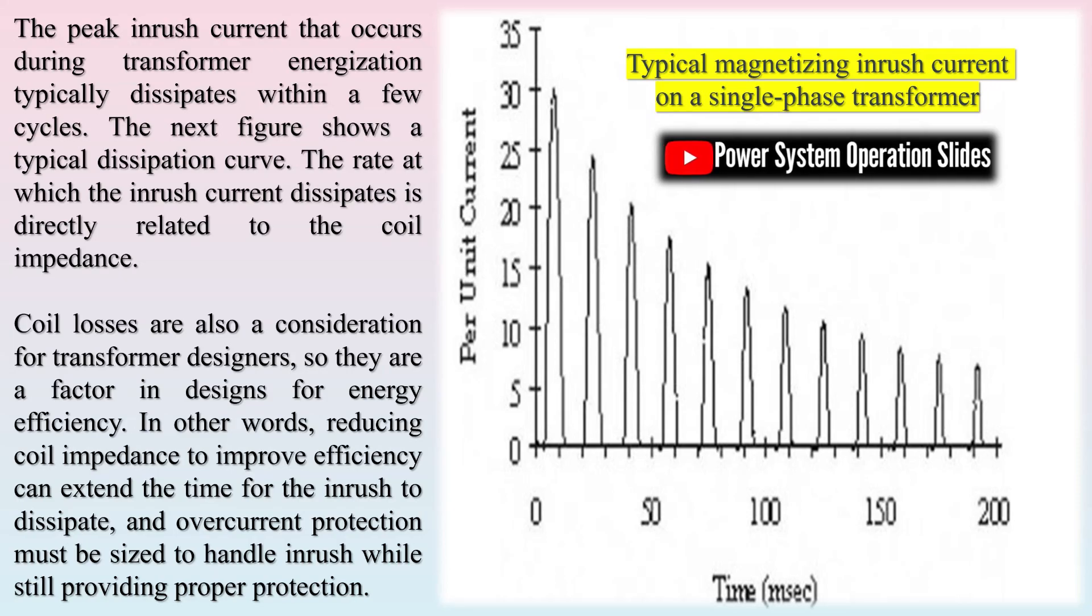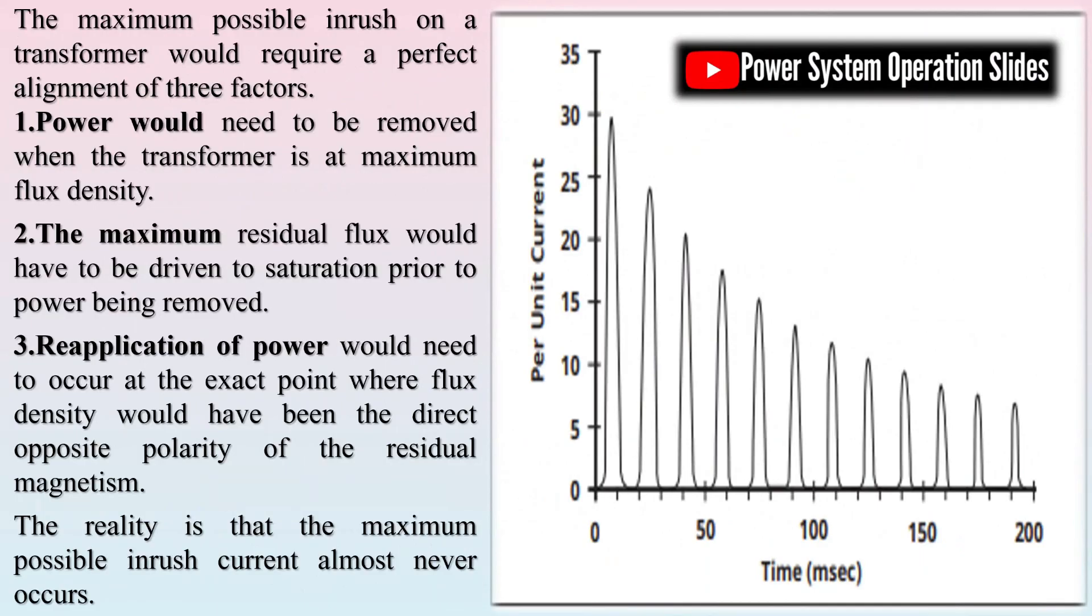This is accomplished by selecting a fuse with a TCC (time-current characteristic curve) which sits to the right of the transformer's inrush curve. Overcurrent protection devices must be coordinated to allow for transformer inrush current. If inrush current is not taken into account when sizing overcurrent protection for a transformer, nuisance tripping may result—breakers or fuses operating as a result of a transformer's exciting current upon energization. The residual magnetism is dependent on where in the hysteresis loop power is removed.